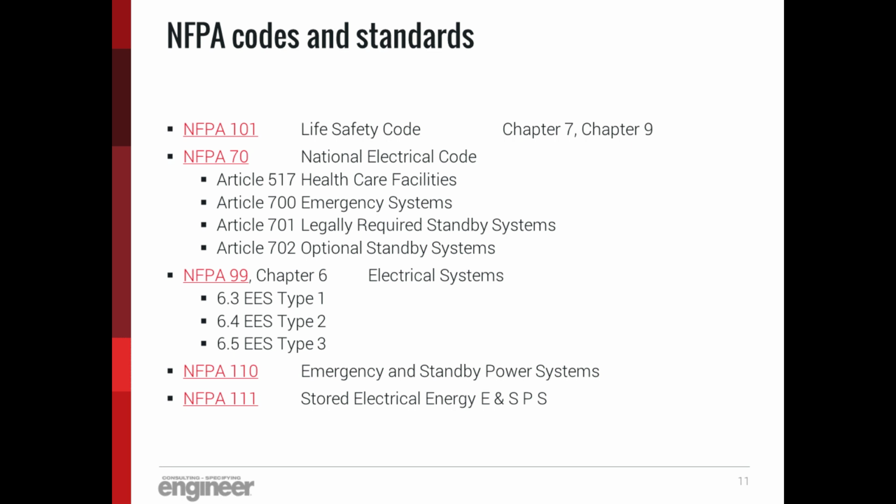So basically, in a case like this, even the 2017 edition, for example, or the TIA that came out in 2017, that's not adopted by CMS because CMS simply is not using that version of the code yet. At some point, the industry expects that CMS will adopt a newer version. The last time it did it, it was notice and comment rulemaking. Notice and comment rulemaking took over a year. It may well be the same way this time.